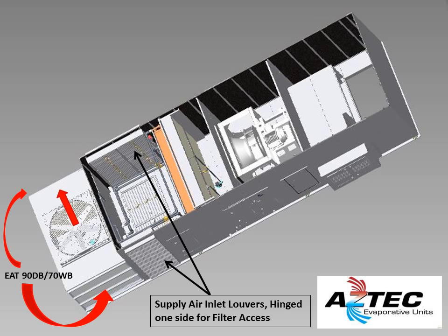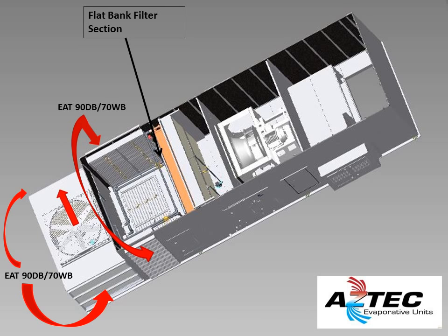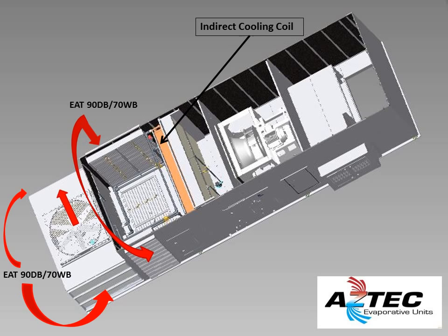Looking at the air handling unit, we have supply air inlet louvers on both sides, with one side being hinged for filter access. We have an entering air temperature through the supply air louvers, same as the cooling tower, of a 90-degree dry bulb and a 70-degree wet bulb. Moving across the unit, we have a supply air 2-inch thick flat bank filter section. Behind the filter section is our 6-row aluminum fin copper tube indirect cooling coil section. The cooling tower provides chill water for the indirect cooling coil. The indirect cooling coil removes sensible heat from the primary outside airstream, providing up to 75% indirect system effectiveness. With this indirect section, water is never in contact with the supply air.